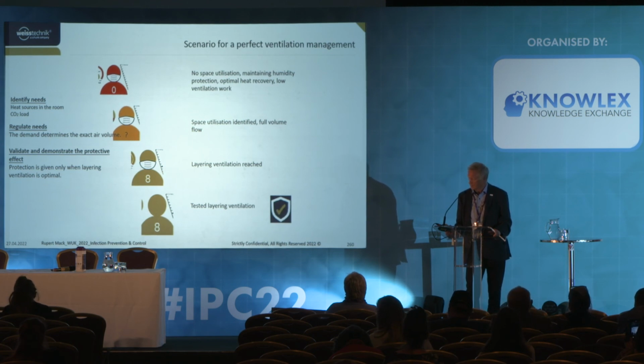A possible scenario: the room is empty, there's nothing and nobody inside. Then you have a sensor that recognizes people coming in, the air volume speeds up to the maximum, and then CO2 measurement starts. According to the CO2 measurements, we calculate the number of people, and so we automatically fix the ventilation flow in order to have needs-based ventilation, which could be an innovative solution.